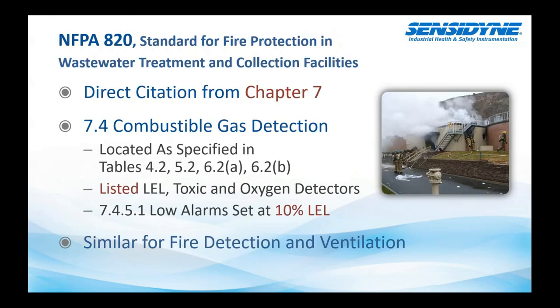NFPA 820 is the standard for fire protection in wastewater treatment and collection facilities. Chapter 7 of that standard, specifically Chapter 7.4, details requirements and placement of combustible gas detectors. Chapters 4, 5, and 6, and Tables 4.2, 5.2, and 6.2 designate the locations, the different codes that are applicable there, and alarm set points.